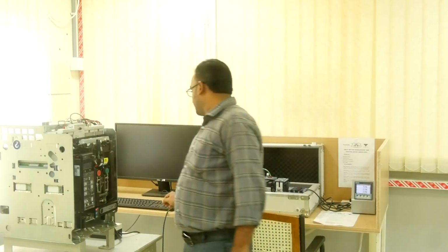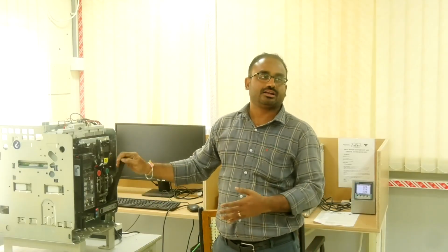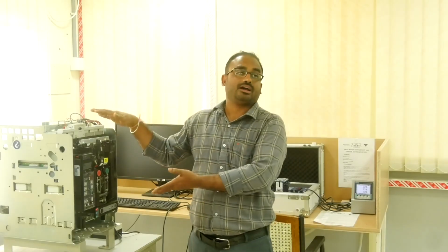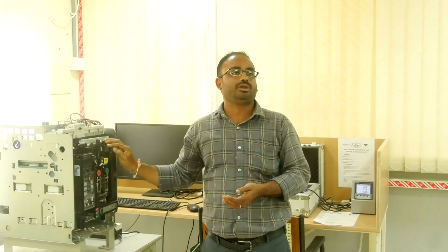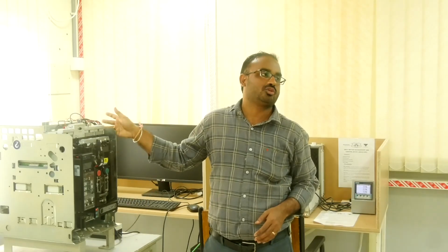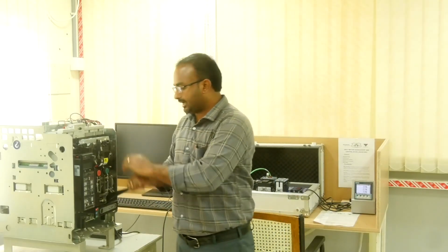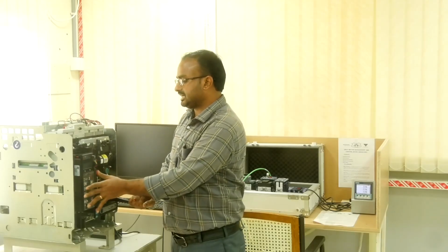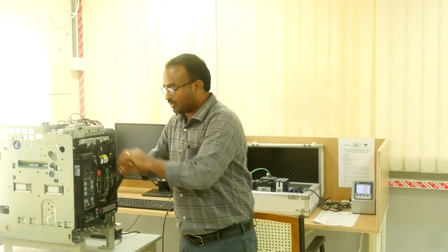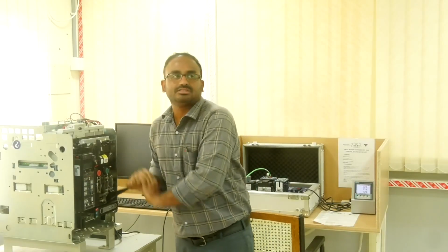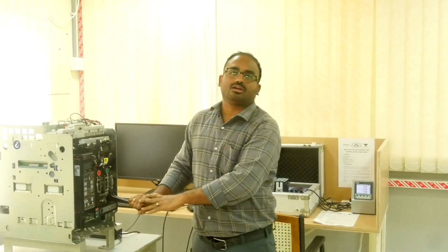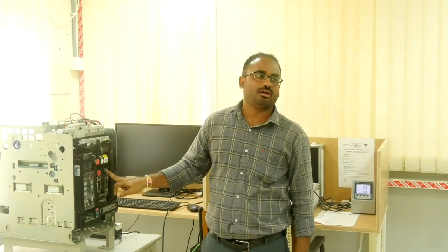Okay, sir. And we also have 2 types of charging. One is mechanically loaded charging and one is electrically loaded. If the air circuit breaker is fitted above the transformer, the operator won't be able to operate it like this to mechanically load the spring. So for that purpose we use electrical loading. If the air circuit breaker is fitted below, near any control panels or the transformer, then they have to operate it like this. This is the discharge condition. Now I have to charge this circuit breaker, the spring will be loaded by the motor operated control. Okay, then it can be operated to on and off condition.